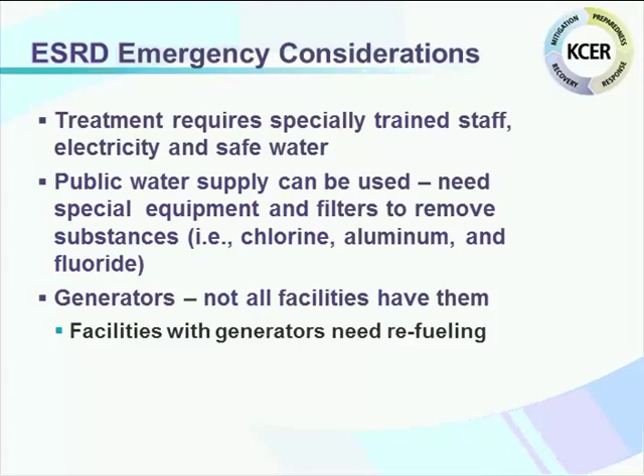During some emergencies, dialysis units are damaged and unable to take patients, so we have to send them elsewhere. We have to have safe water. Any type of public water supply can be used, but we have to filter that water with a special reverse osmosis machine to remove substances such as chlorine, aluminum, and fluoride. These substances, if not removed from the water, can leach into the patient's bloodstream through the hemodialysis filter.